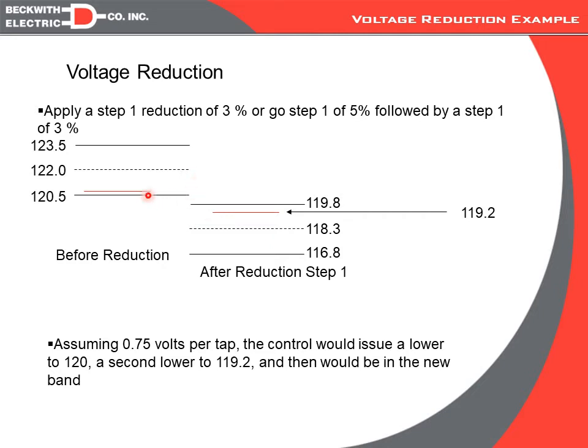But we'll also notice that we still won't get the full 3% that we've requested. So if we started at 120.7, when we issue our first lower, 3/4 of a volt per tap, that still puts us right above the band. So we're going to have to take a second tap, and we'll finish up at about 119.2. So for this 3% reduction, we started at 120.7 and we finish at 119.2.